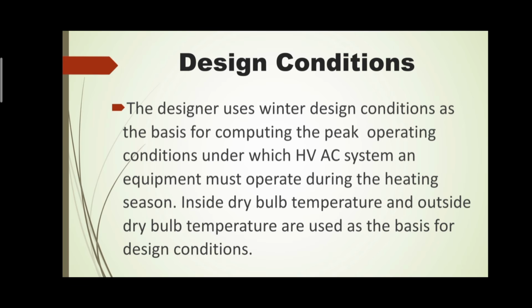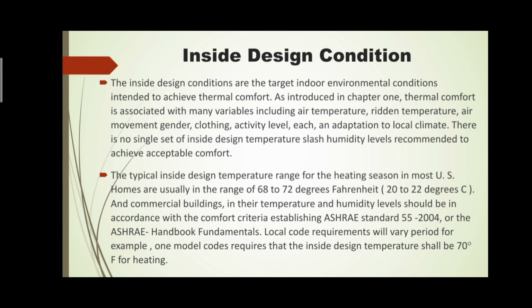Design conditions. Designers use winter design conditions as the basis for computing the peak operating conditions at which HVAC system and equipment must operate during the heating season. So, yung mga designer, gumagamit sila ng winter design condition para malaman nila kung hanggang gaano ba kainit or gaano ba kalamig yung aabutin sa isang lugar on a certain place and on a certain period of time. Inside dry bulb temperature and outside dry bulb temperature are used as the basis for the design condition. So, ayun nga, yun yung mga ginamit na basis for design conditions.